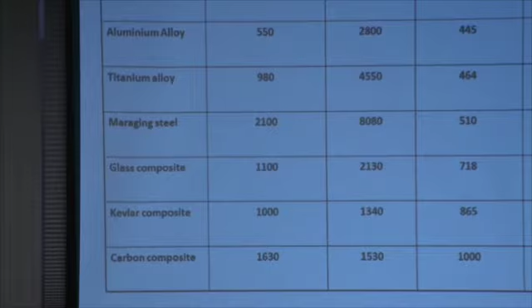Now I mentioned you want to get the speed up. Well, that really depends on the material. Some materials can withstand higher speeds, others can't. And at some speed, all these materials are just going to fly apart. The first material developed for centrifuges was an aluminum alloy, and it could have a speed up to 445 meters per second, but aluminum has an undesirable property that when it's spinning, it tends to creep and move. And what that meant, if you're up at the higher speeds, the centrifuge will break within a year. And so the operational speeds of these aluminum rotors are down around 350 meters per second.